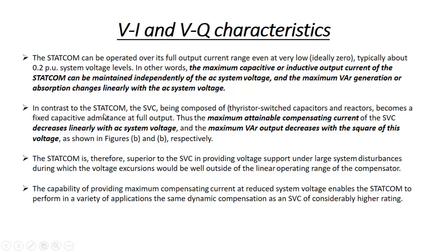In the case of the SVC, composed of thyristor-switched capacitors and reactors, it becomes a fixed capacitor admittance at full output. The maximum attainable compensating current of the SVC decreases linearly with the AC system voltage because current depends on voltage. The maximum VAR output, equal to V² divided by Xc or V² times Bc, decreases with the square of the voltage.